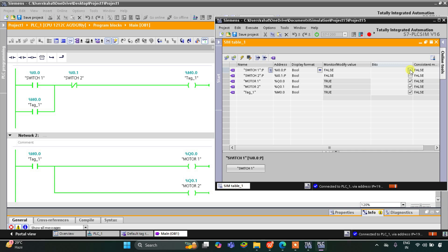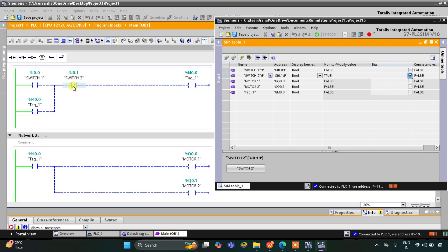When I turn switch 1 off, due to latching M0.0 is still true. The current flows through it. Switch 2 is in false state and as a normally closed contact the current flows through it, so M0.0 remains on, which in turn keeps motor 1 and motor 2 on — these motors still remain on. Then when I turn on switch 2, as it is a normally closed contact in true state it will not allow current to flow. M0.0 turns off and as a result motor 1 and motor 2 turn off. That was all about this example. Thank you for watching.